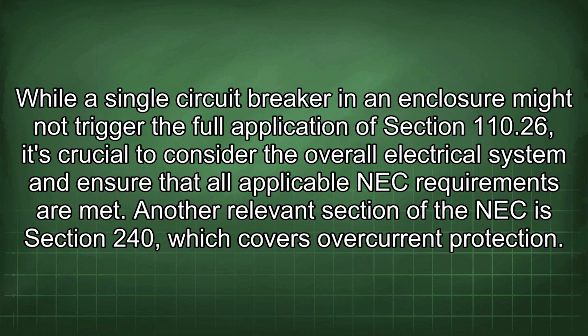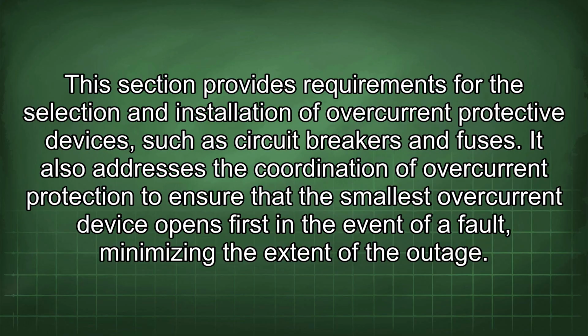While a single circuit breaker in an enclosure might not trigger the full application of Section 110.26, it's crucial to consider the overall electrical system and ensure that all applicable NEC requirements are met. Another relevant section of the NEC is Section 240, which covers overcurrent protection. This section provides requirements for the selection and installation of overcurrent protective devices, such as circuit breakers and fuses.